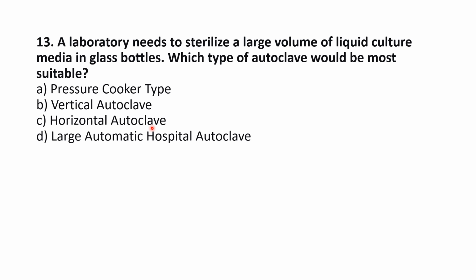Now, the large automatic hospital autoclave, which is our D option here, could also work, but the horizontal autoclave is a standard type for this purpose. The pressure cooker type is a small benchtop unit and not suitable for large volumes. And then the vertical autoclaves are more compact and are loaded from the top, which can be cumbersome for large heavy bottles. For the large automatic hospital autoclave, well, potentially suitable, but the horizontal type is the classic design for this application in a lab context.